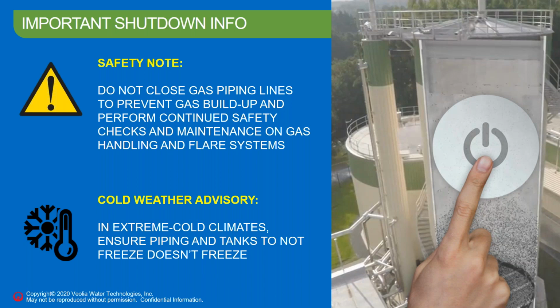And even when the system cools down, especially if you're going to shut down this time of year when it's cooler, and you all know from previous webinars that as the temperature goes down, the activity of the sludge goes down, you're still going to make gas even under those conditions. And you want to be able to discharge that gas in a safe manner. So you need to keep the biogas lines open and at least the lines open to the flare.